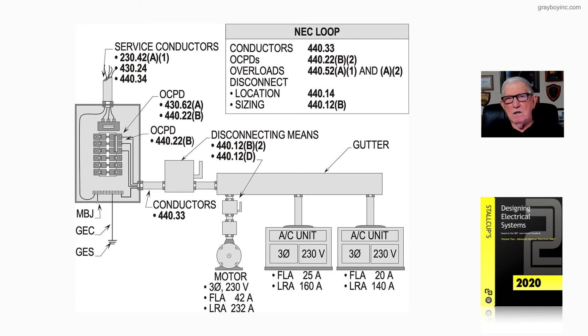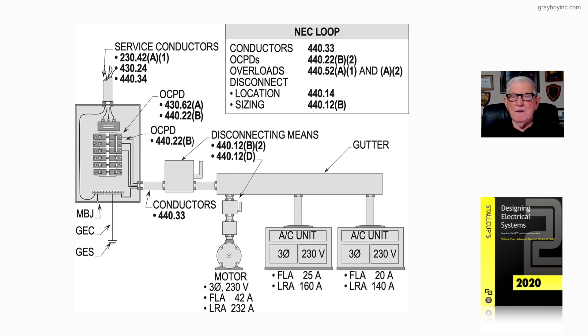It's a three-phase 230-volt motor. The FLA running current could be up to 42 amps, and the locked rotor current would be 232. For the AC units: the first has an FLA of 25 and LRA of 160; the second has an FLA of 20 and LRA of 140.